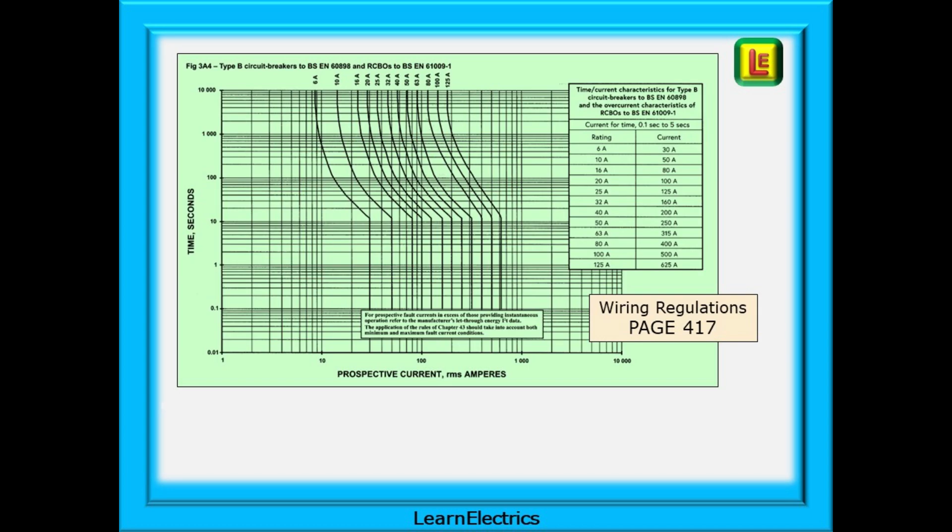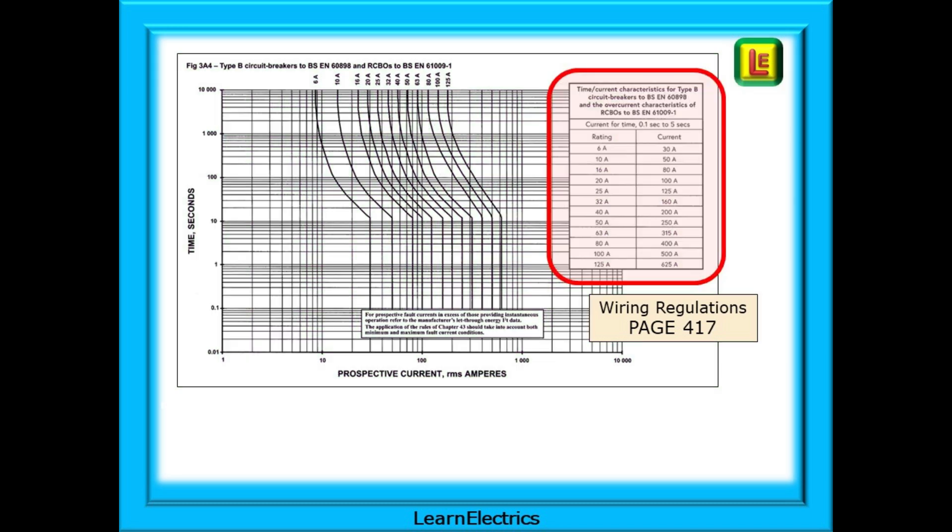On page 417 of the wiring regs you will find this chart called figure 3A4 which is for the type B circuit breakers to BS EN 60898 and RCBOs to BS EN 61009. Each breaker type and fuse type in current use will have a page in Appendix 3. We're interested in the chart at the top right.